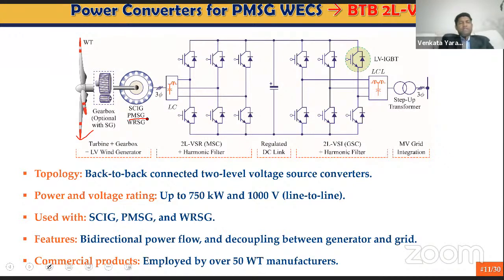It converts AC to DC, and then here we have a regulated DC link. The DC is converted back to AC by the 2-level voltage source inverter. If we look at the construction of the 2-level VSR and the 2-level VSI, they are identical. The switching devices are implemented by low voltage insulated gate bipolar transistors. The output is connected to the step-up transformer through a harmonic filter like an L filter or LCL filter, and then the output of the step-up transformer is connected to the wind farm collection point.